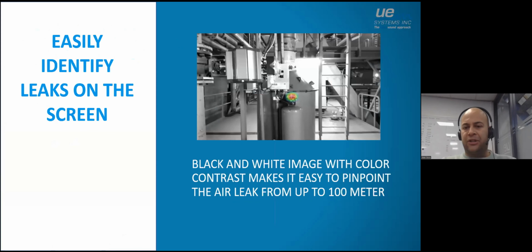All right, so here is another picture I took with the camera, and you see a compressed air application, and you know where the leak is because you see the hotspot over there. The background is black and white, and if there is a phenomenon like a leak, you see a color, and that makes it easy to find. And the air leak from up to 100 meters, well, of course, that's in the perfect situation, but I did a test once, and I found a leak from 65 meters distance. Could you imagine you're standing on the other side of the hall and you find a leak? That's 65 meters further down the road.